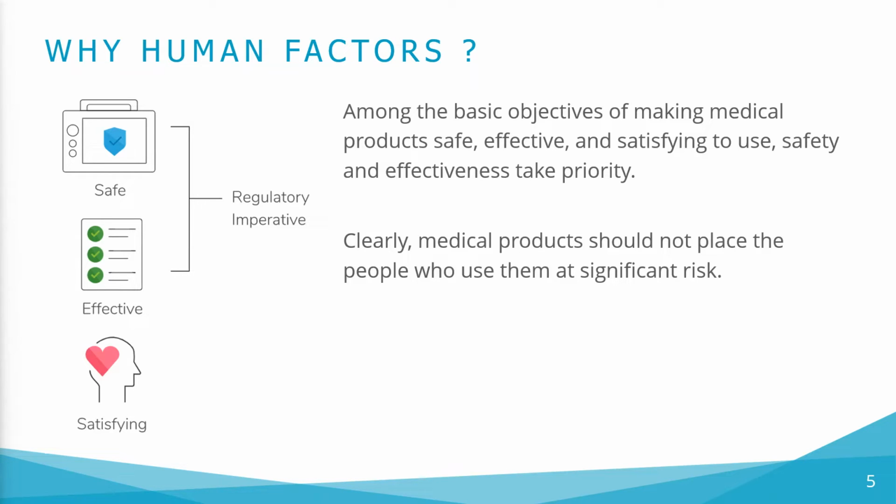Today, we are seeing a convergence of 100 plus years of HFE progress and a critical need to reduce medical error, specifically regarding interactions with medical products. Therefore, we speak of a regulatory imperative to apply HFE during the development of a medical product. It's an imperative, meaning it is mandated. Otherwise, a manufacturer might not receive a clearance or approval to market its device.